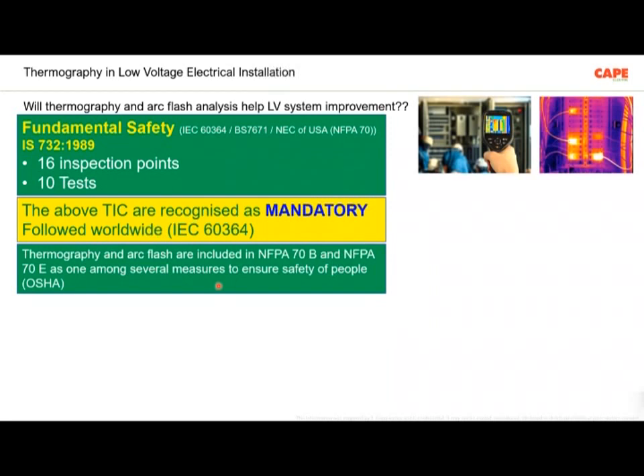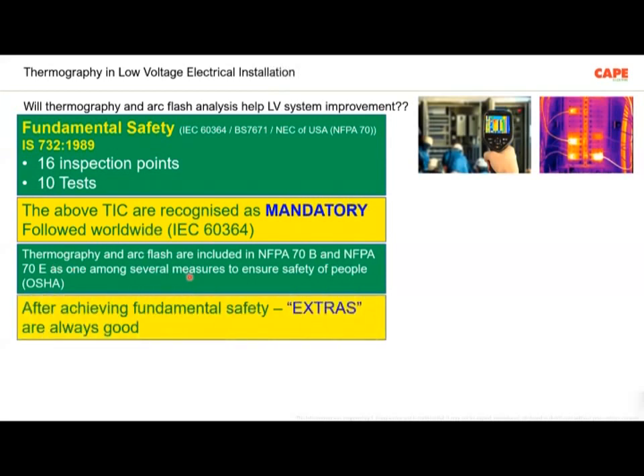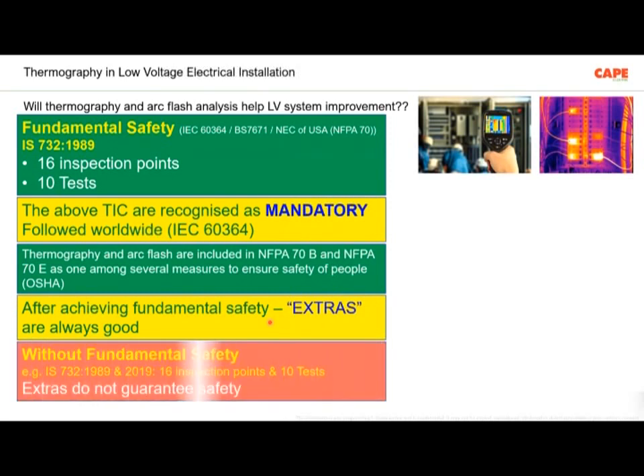Thermography is not the only one. Arc flash study is not the only one. These are considered one among the several safety measures. But fundamentally, you have to have this 16 plus 10, which is mandatory. And the additional things, thermography and arc flash, these are, let me say, extras. After achieving fundamental safety, extras are always good. Extra tests ensure additional safety for you.